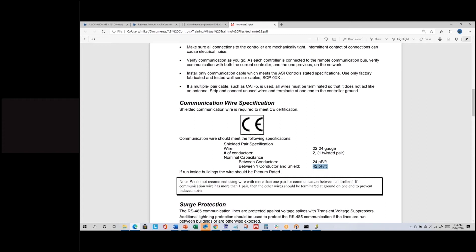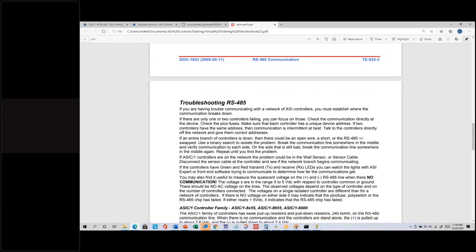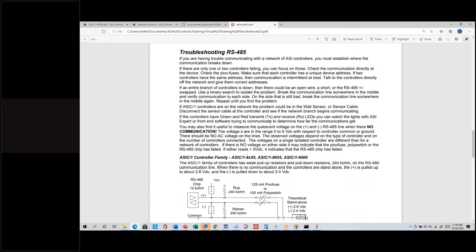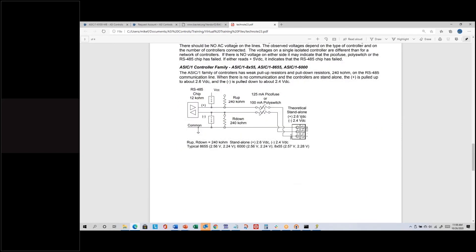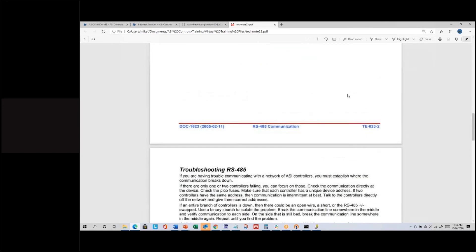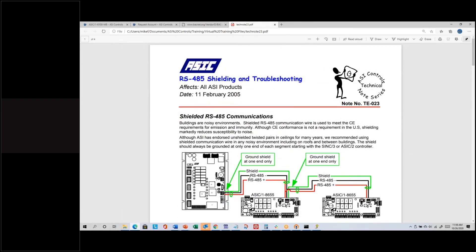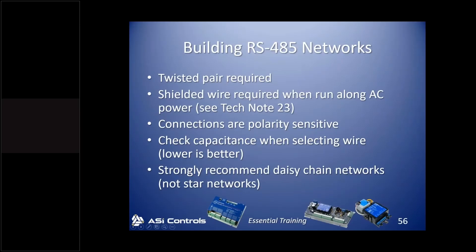Lower capacitance wire tends to be more expensive. There's another mention of not using more than one pair, and if you do have more than one pair, terminate them as if they were the shield wire. The document goes on with more technical information about measuring voltages, which I haven't found very useful, but the information on the first couple of pages is what I refer to — that covers the RS-485 network recommendations.